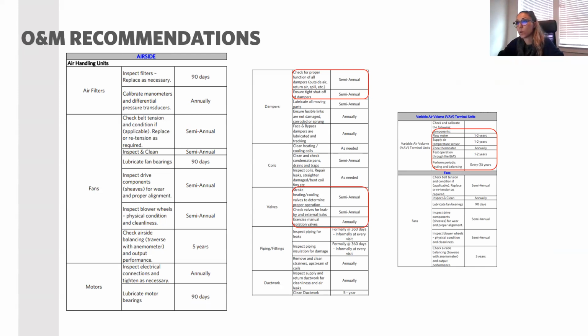So that's a segue to the O&M. That's why we always include O&M recommendations for each building. This one is only focusing on the air side, but the building may also have a central plant. We always include O&M recommendations in our report, because that is what is going to make these controls actually work. Like the previous example I showed about chilled water reset, it was relying on either the discharge air temperature sensor to be working correctly, or the valves operating correctly. So if you don't make sure these sensors and valves get semi-annual or 1 to 2 year maintenance, then there's no way these controls will work correctly.